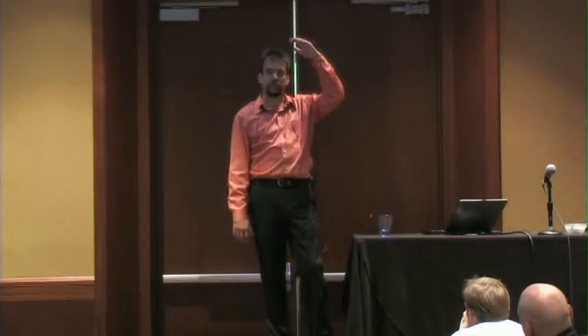Just looking at a site a couple of days ago that we thought was going to be a great install for heat containment, and it was a brand new install, and the cable tray system went in, and I've got all these perpendicular wire trays. I'm like, okay, now we're going to hit a problem there, or there's not enough height. They put it in an existing office building. You have like an 8 to 10 foot deck height from the pad to usable space. Well, you want to put in a 48U rack and then try to have a return bottom. It's problematic. So there are a variety of different containment strategies, and site constraints would dictate which one's best for deployment. But again, the whole idea is separation of hot and cold.